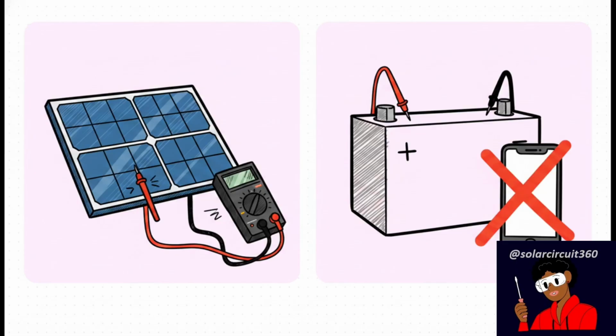Let's break down those first 2 steps, verifying array voltage and battery voltage. Step 1 is taking a DC voltage measurement straight from the array before the power ever hits the charge controller. This confirms your panels are wired correctly and, crucially, verifies the polarity. If you skip this and the polarity happens to be reversed, boom, you destroy the equipment.